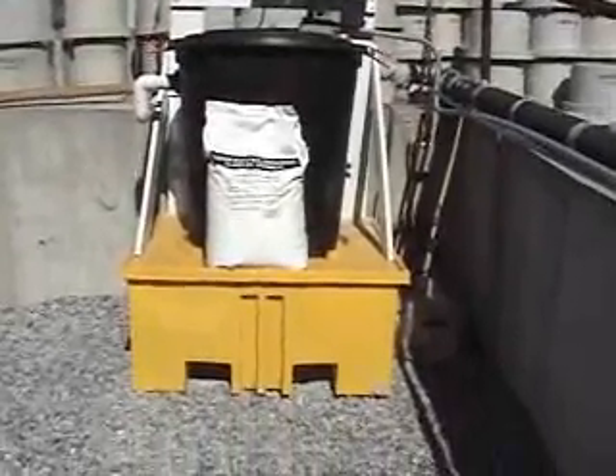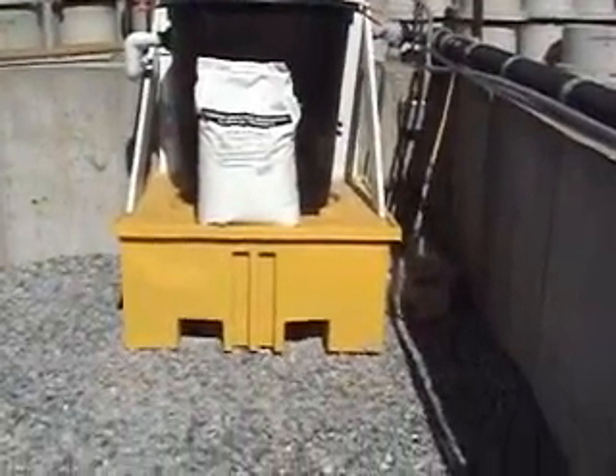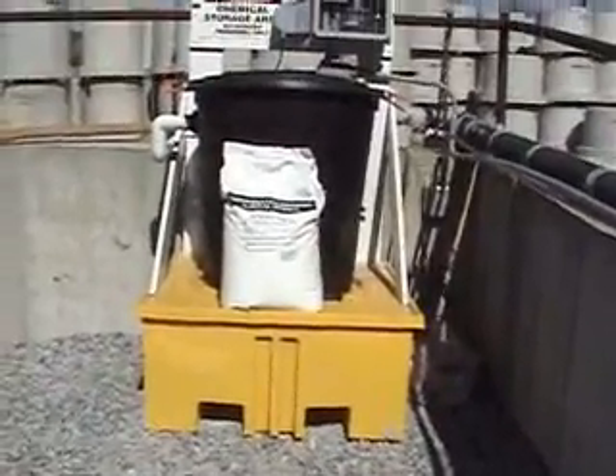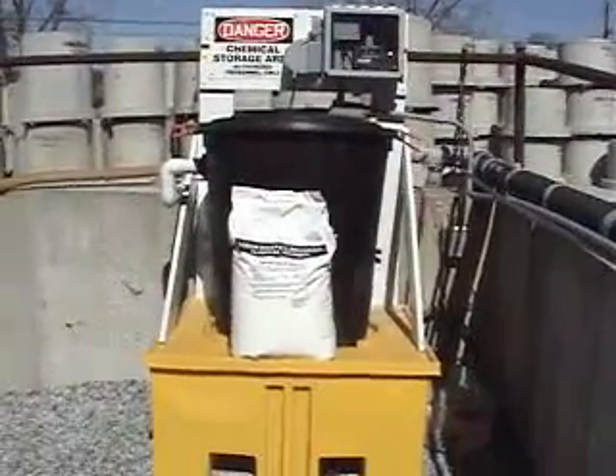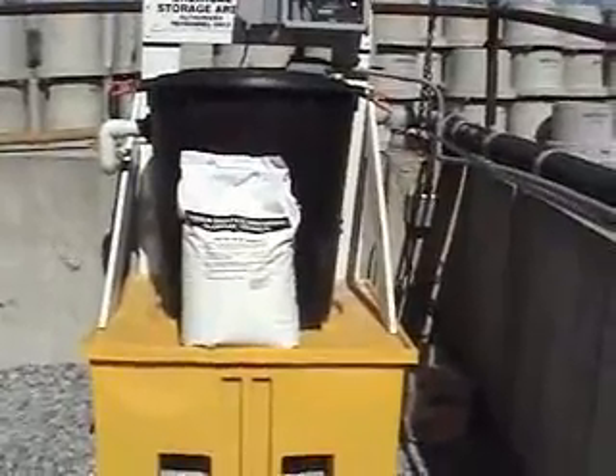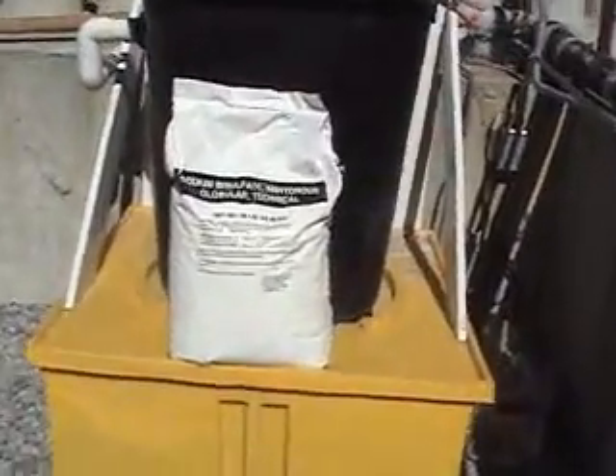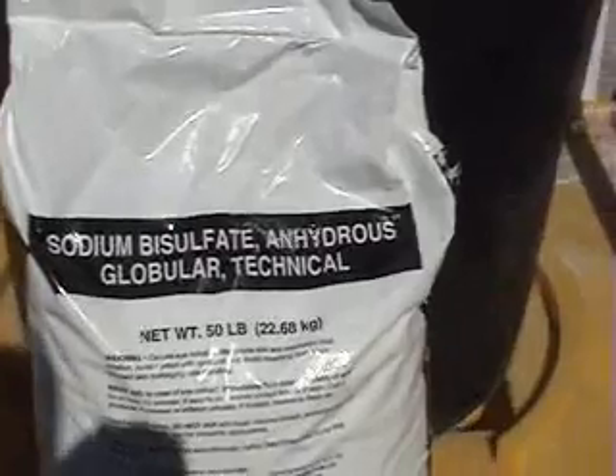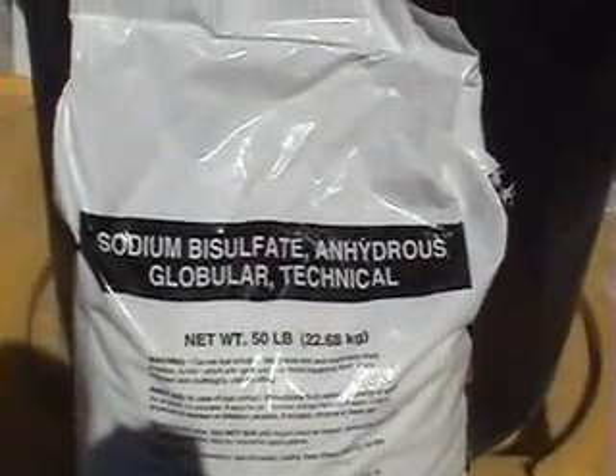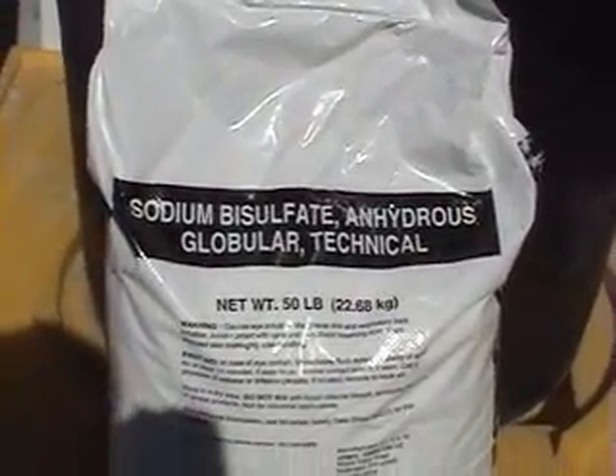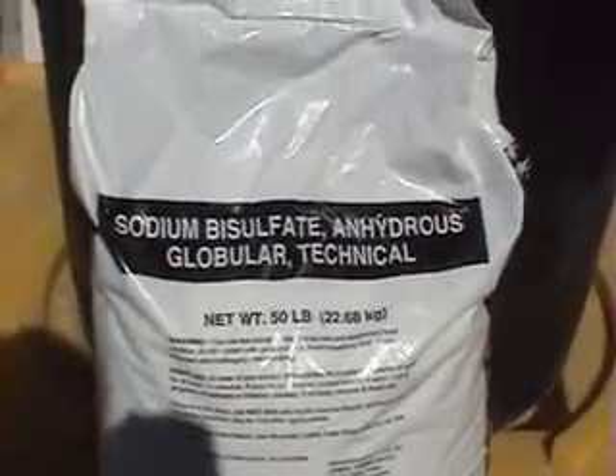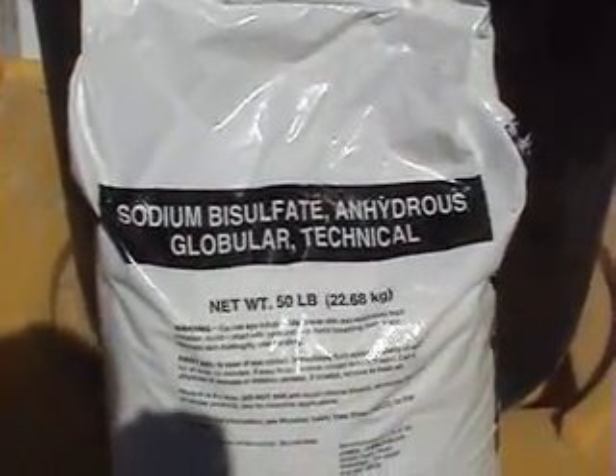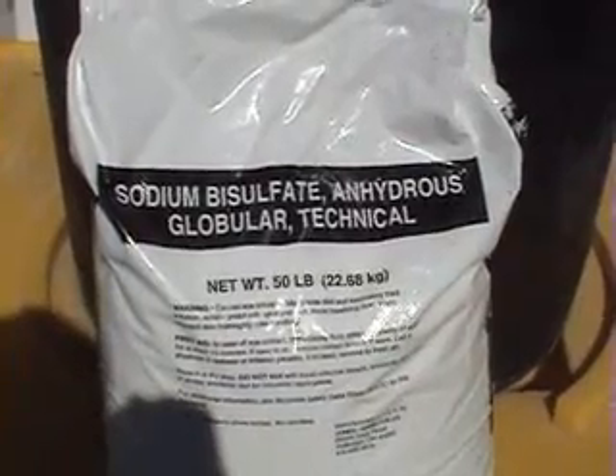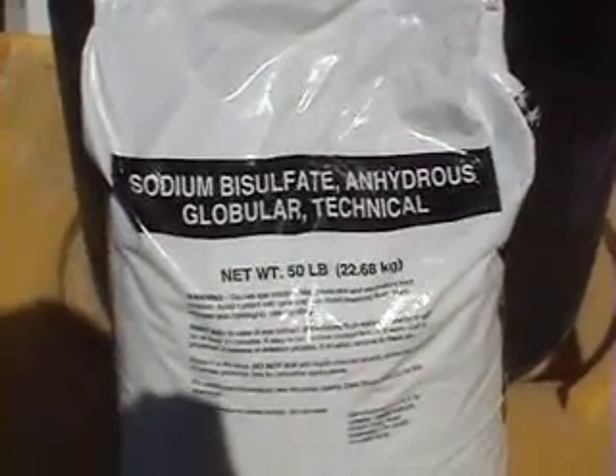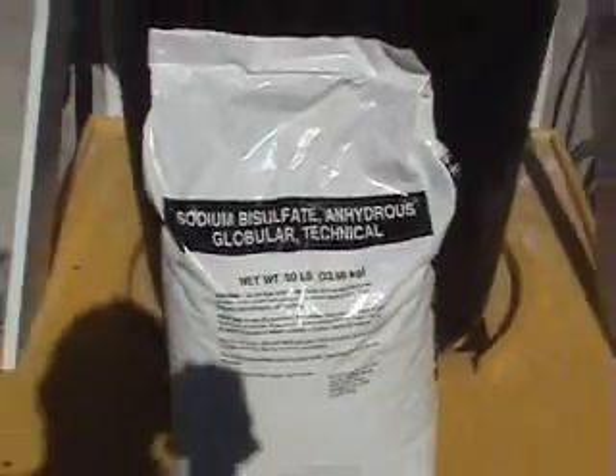Okay, just a quick recap of our pH WatchDog and all of its components. Again, you have your base of the system, which is a secondary spill pallet for safety reasons. On top of that, you have your black mixing drum or storage drum, which holds our sodium bisulfate. Here we have a small 50-pound bag of the sodium bisulfate, which is a granular dry acid and is only activated when wet or in water, and is actually labeled as an irritant rather than a hazard. So very, very safe and effective way of treating pH.